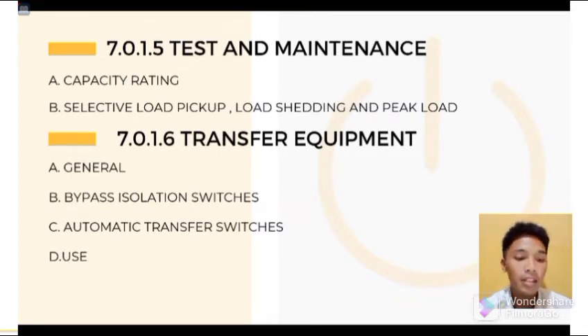Okay, next will be 7.0.1.5, capacity. A. Capacity and rating. An emergency system shall have adequate capacity and rating for all loads to be operated simultaneously. The emergency system's equipment shall be suitable for the maximum available fault current at its terminals. Letter B, selective load pickup, load shedding, and peak load shaving. The alternate power source shall be permitted to supply emergency, legally required standby, and optional standby system loads where the source has adequate capacity, or where automatic selective load pickup and load shedding is provided as needed to ensure adequate power to: 1. The emergency circuits, 2. The legally required standby circuits, 3. The optional standby circuits, in that order of priority.